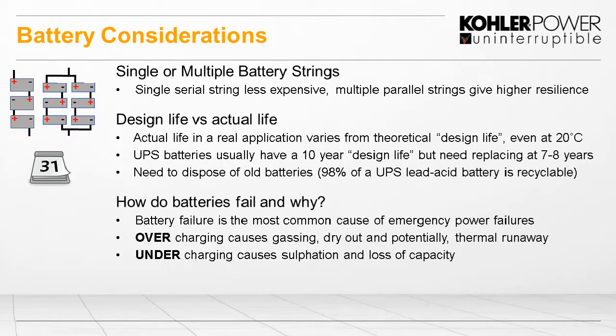Now, battery failure is the main cause of UPS failures, and batteries fail either by being overcharged or undercharged. Now, overcharging causes the battery to gas, to dry out, and if left in that condition, will run into thermal runaway. Obviously, a serious condition. If they're undercharged, this causes sulfation and loss of capacity of the battery itself.